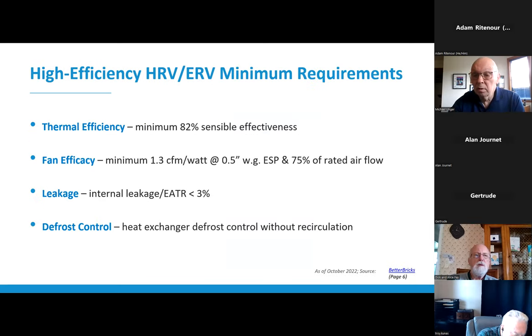There are 4 of them. The first one, of course, is that minimum 82% sensible effectiveness for thermal efficiency. NEA also requires a fan efficacy of at least 1.3 CFM per watt at certain design conditions, and a low internal leakage rate, so an exhaust air transfer ratio of less than 3%. This is really important for NEA since one of NEA's main goals for this type of HVAC system approach is high indoor air quality. And the last minimum requirement is heat exchanger defrost control without recirculation. And again, that's for the high indoor air quality requirement that NEA is going for.